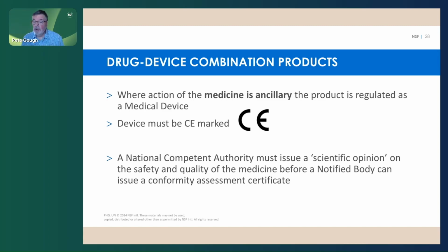It would be perhaps more complicated if that medicine that's been added to your device as an ancillary action did not have a marketing authorization separately for the medicine. But again, you would need to get a scientific opinion from a national competent authority before the medical device notified body could issue the conformity assessment.